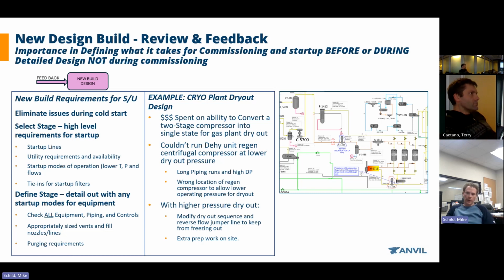The startup modes of operation. Sometimes when you're starting up, you're going to be bringing equipment up, you're going to be shutting it down, you have to do hot alignments. So you're not going to have your full flows usually initially. Also, you might be operating at lower temperatures and pressures, so you got to be mindful of that. Startup filters: we really like to filter our liquid lines, and if we don't have filters in that line, we might be putting witches hats in there, or we might be providing valves to bring in temporary filters to start filtering out these lines and cleaning them up.